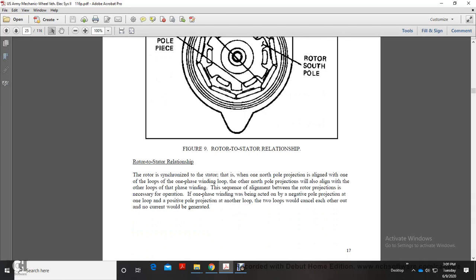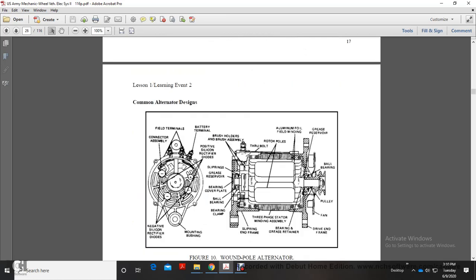Rotor to stator relationship. The rotor is synchronized with the stator, with a north pole projection lining up with the loops of one phase winding and the other north pole projection also lining up with the other loops of the phase winding. This sequence of alignment of the rotor projections is necessary for operation. If one phase winding were acted on by a negative pole projection at one loop and a positive pole projection at another loop, the two would cancel each other out and no current would be generated.